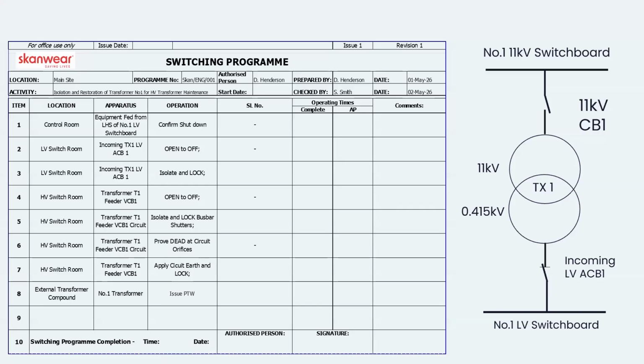So we typically have: whose is the switching program, where is it, what is it, when are you doing it, and what is the activity you're going to be conducting. Your risk assessment would typically back this up as well. One person would normally draft this—you might do this in pairs depending on your electrical safety program. Essentially, your plan is just a sequential process of isolating that system to achieve safety from the system to conduct the task you've documented.